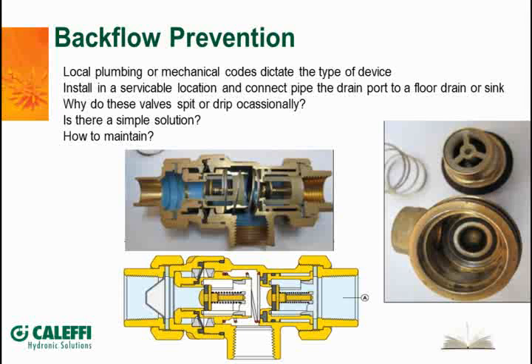Now, this is required in most places. It's a code-required device that goes on any application where you're putting boiler water in. Certainly, if you have glycols or chemicals that you're putting into the system, you want to make sure you've got the right listed backflow preventer, so that if there was a low pressure condition in the house or in the water system, the public water system, those fluids can't go back into the water system. So typically what we're going to use is what we call a double check valve. This is called a dual check backflow preventer.